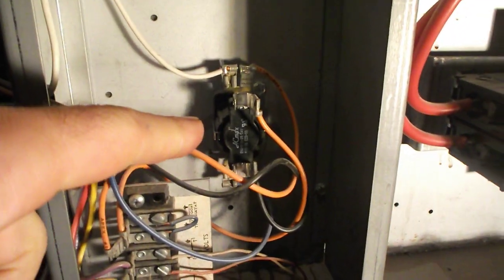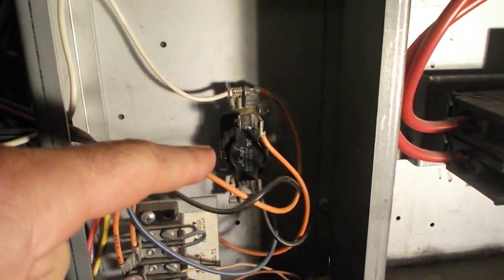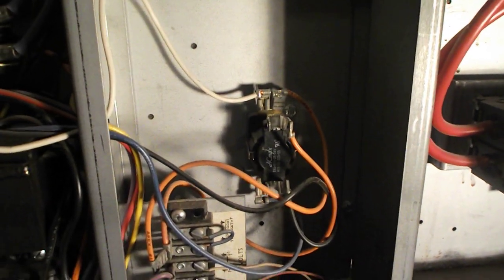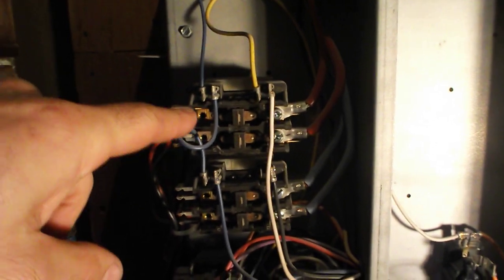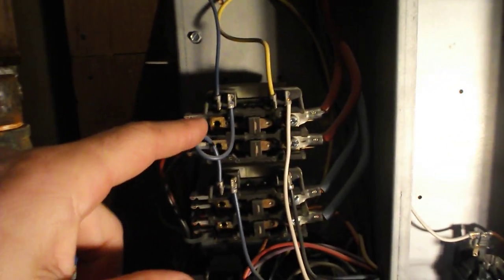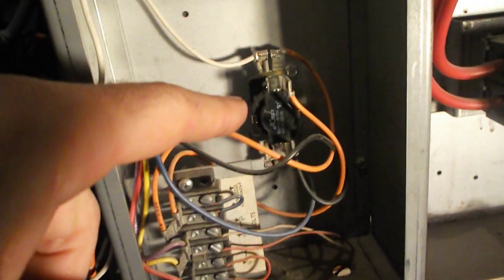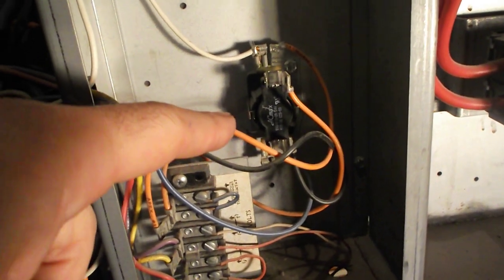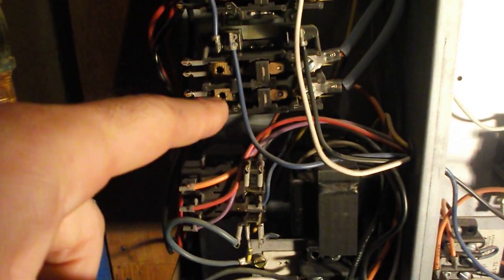This device right here is a time delay relay. So when the heater cuts in, the large set of contacts activate first, and that triggers the high current element right away. But this device right here is a time delay relay, and after about 30 seconds, it will trigger this second set of contacts to cut in.